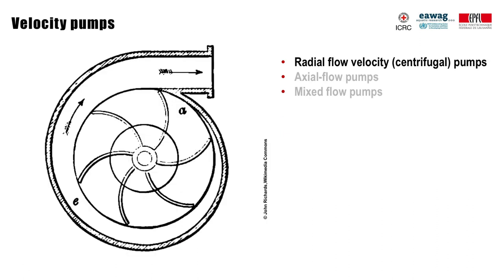While positive displacement pumps operate by manipulating the available space inside the pump, velocity pumps operate by manipulating the velocity of fluid during its movement through the pump. A radial flow pump, also known as a centrifugal pump, first converts energy of a motor into kinetic energy by a rotating impeller. When the impeller rotates, it spins the water sitting in the cavities between the vanes outward and provides centrifugal acceleration. As water leaves, a low pressure area is created, leading to suction of more water. The kinetic energy of water coming out of the impeller is afterwards harnessed by creating resistance to the flow. Water meets with a stationary diffuser or volute, which slows it down and converts the kinetic energy into pressure energy.